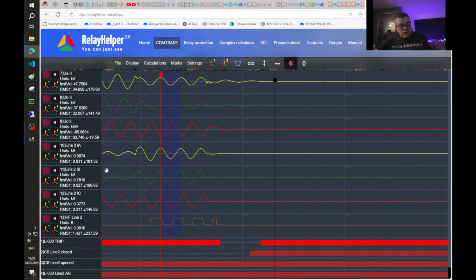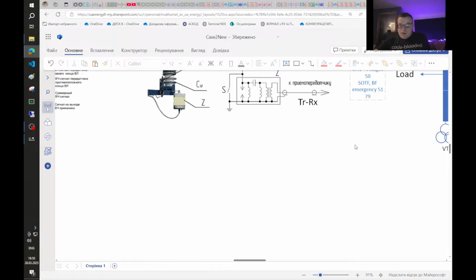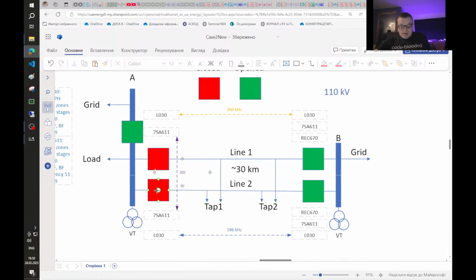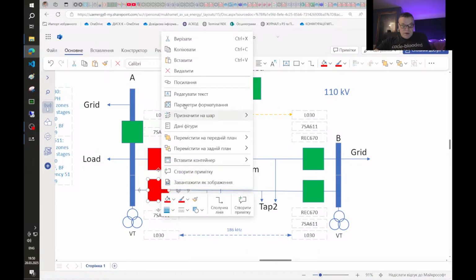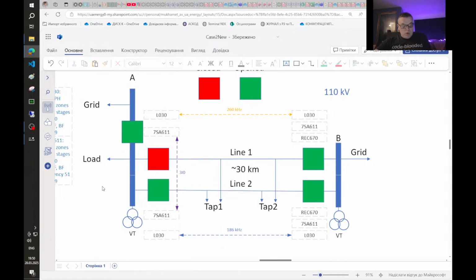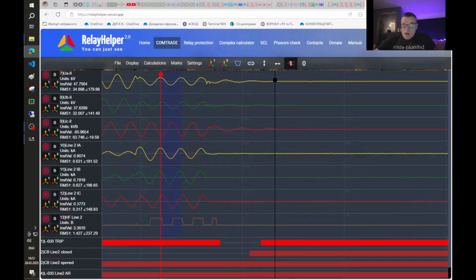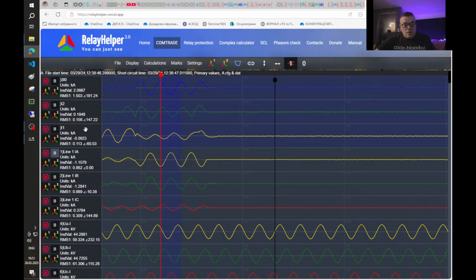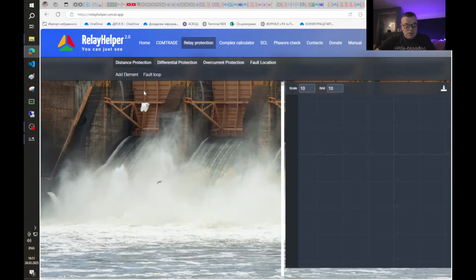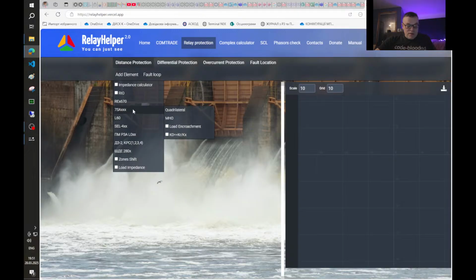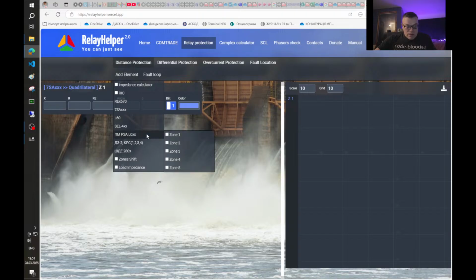So from substation A side, at least this circuit breaker was tripped by phase differential protection from L30. So let's check distance protection. Let's return here. So I need to manually insert settings.